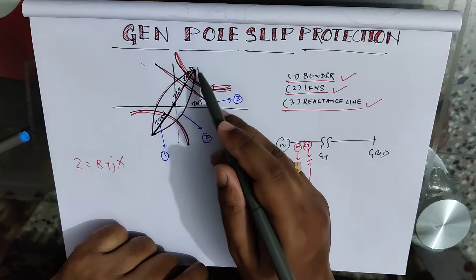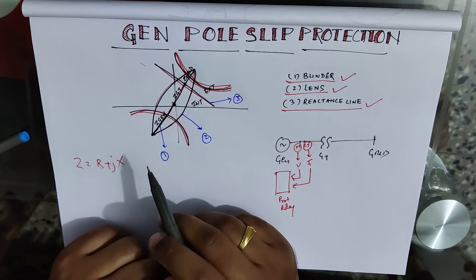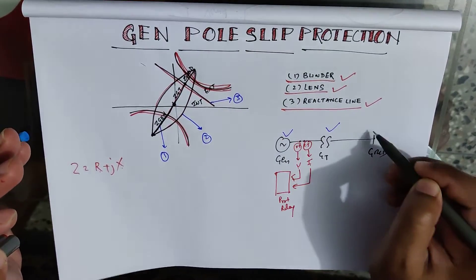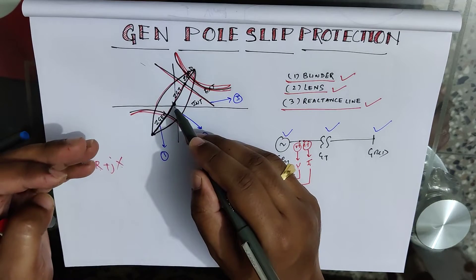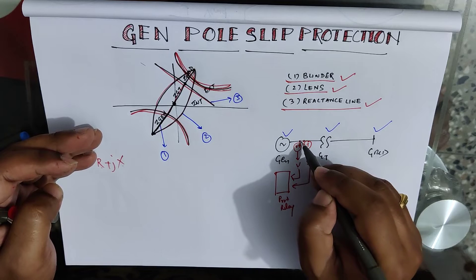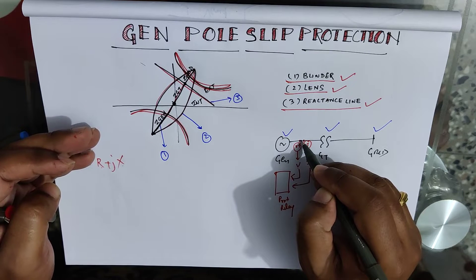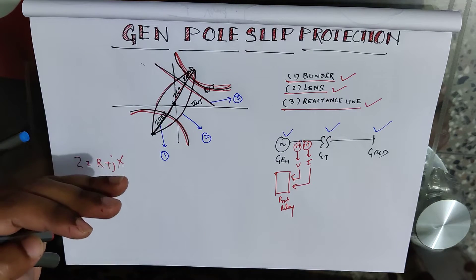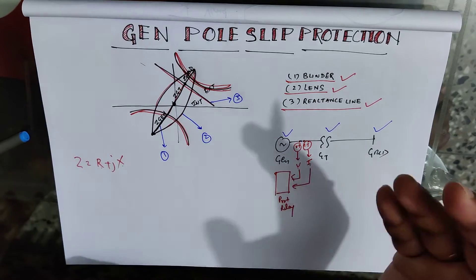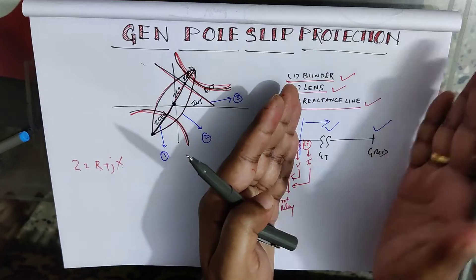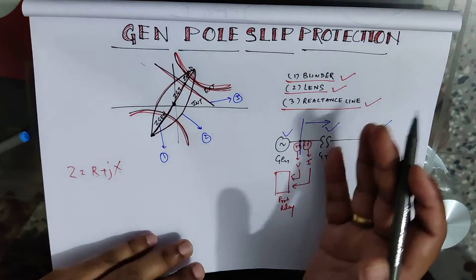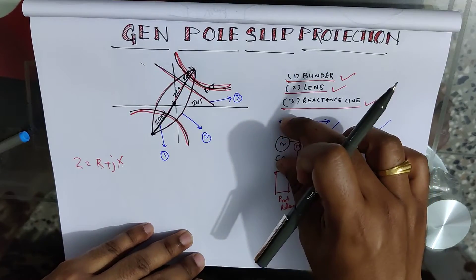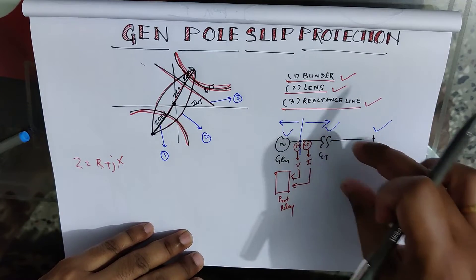The blinder represents the impedance of three parts: generator, GT (generator transformer), and grid. As it crosses through the origin — which is the terminal point of the generator — the relay senses two kinds of impedance: forward impedance (after the sensing point) and backward impedance (before the sensing point). The backward part is the generator part, and the forward part represents GT and grid impedance.